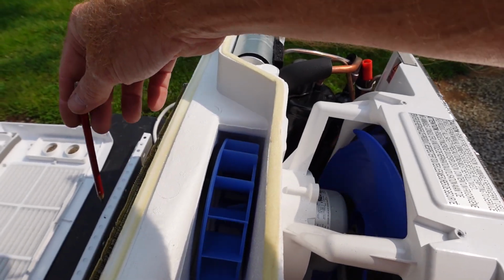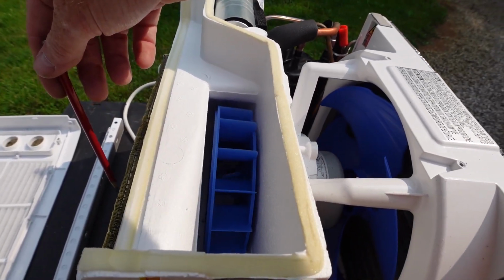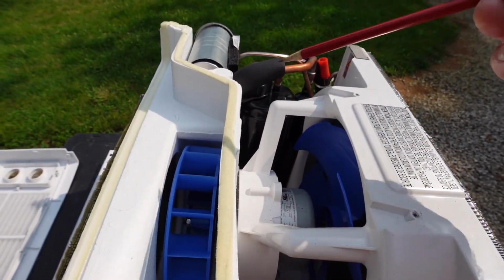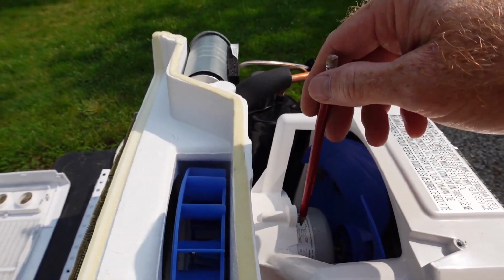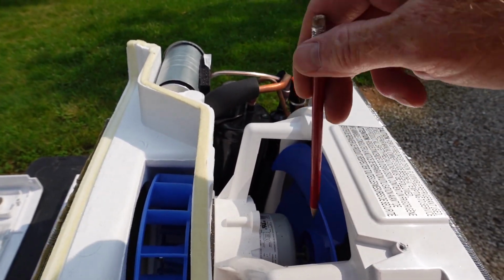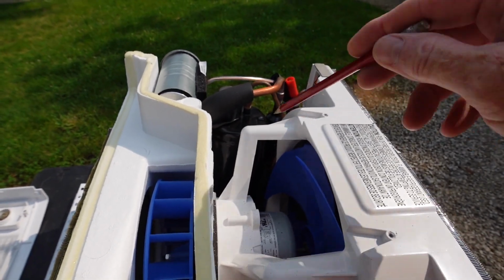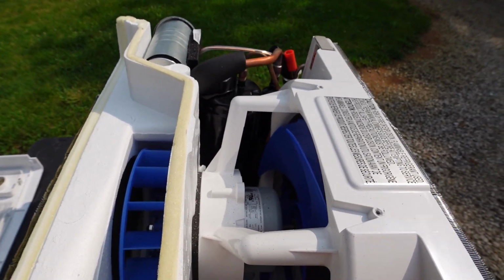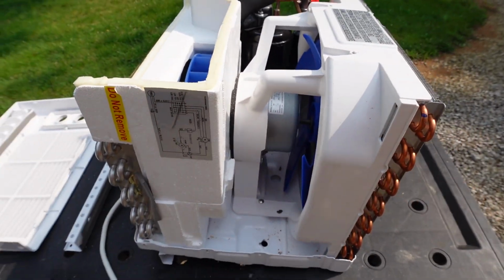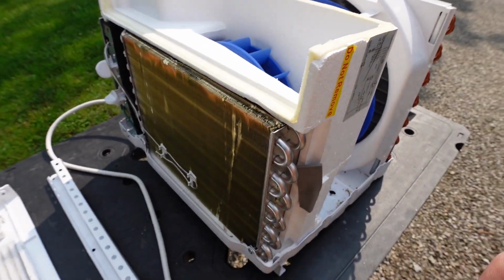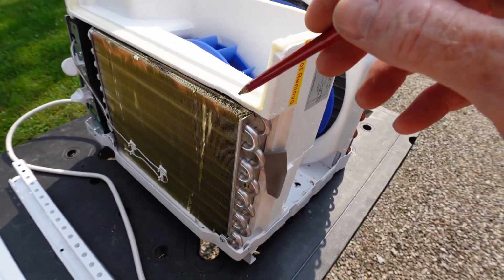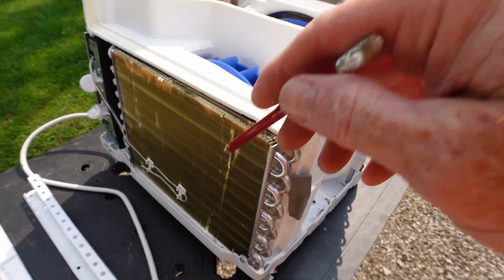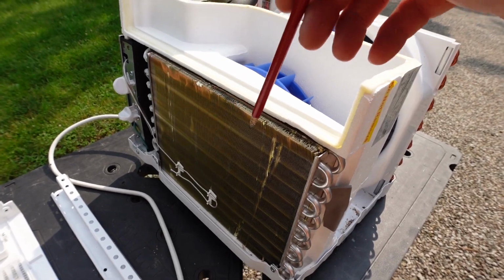And it's going to draw the return air in through your evaporator coil up here, bring it through here, cool it down, and then eject it out the top. And then the back fan, the same motor, the back shaft of it is what drives the fan for the compressor that helps cool the compressor, which is over here, and then also moves that air through this condensing coil back here in the back. Now, you will get more condensation on this front coil on the inside of the house, because that's where your hot, humid air hits the cold refrigerant running through this coil.